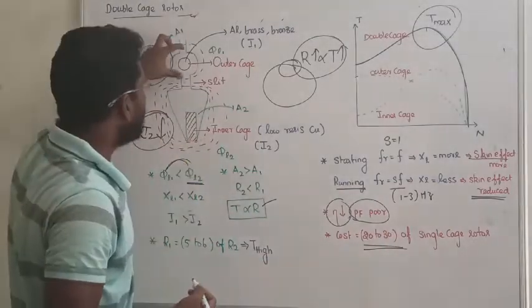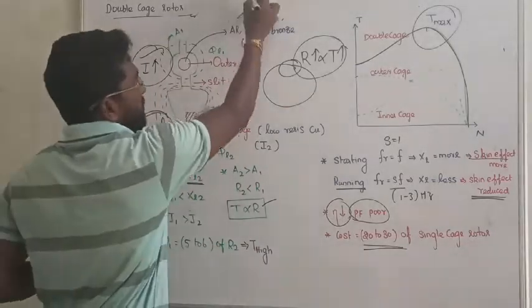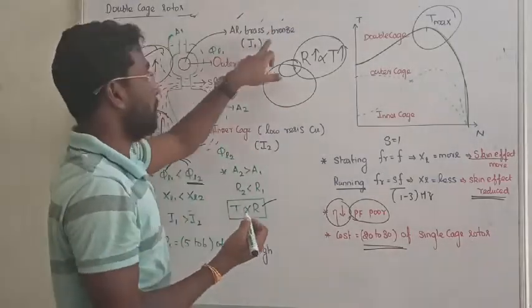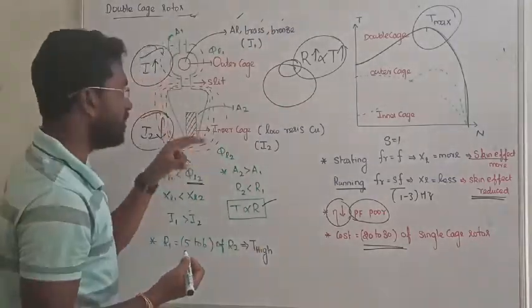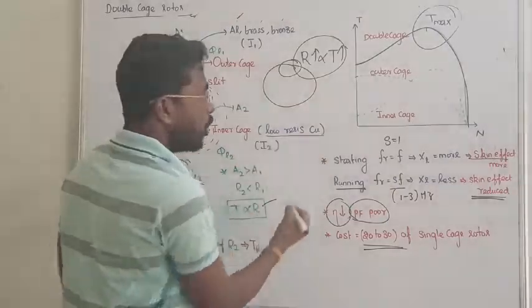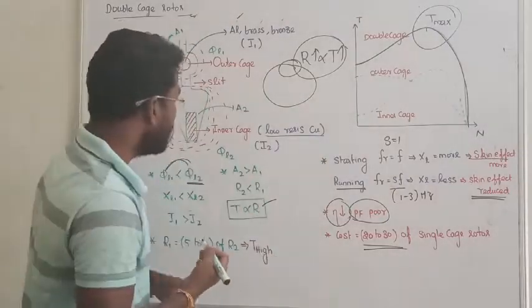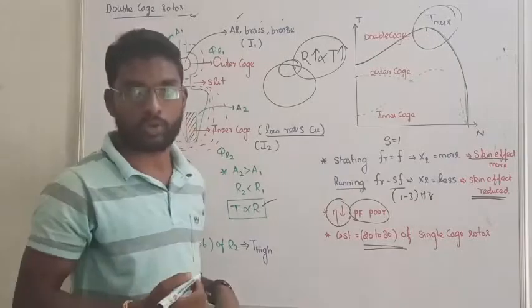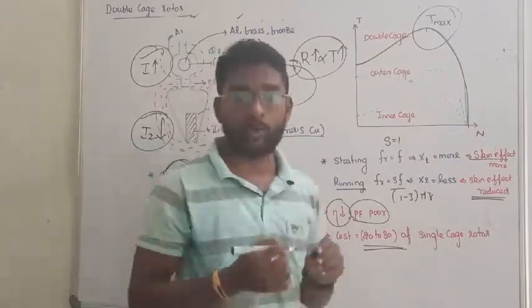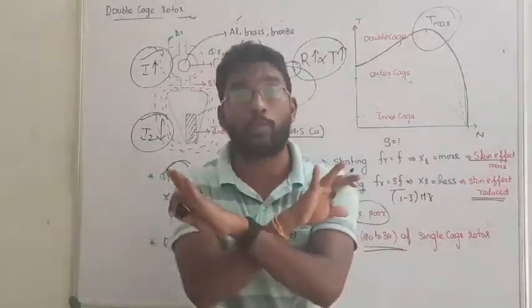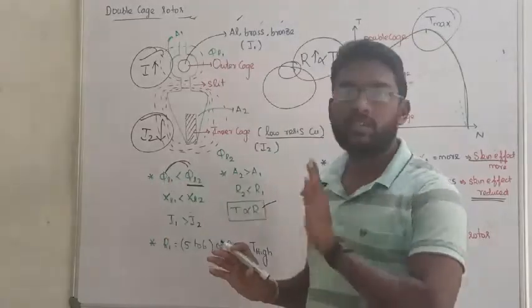So that is all about double cage rotor construction. Here the outer cage, for high resistance, we are using special type of materials like aluminum, brass or bronze. We are using low resistance copper conductors for inner cage. That's all, this is all about double cage rotors.